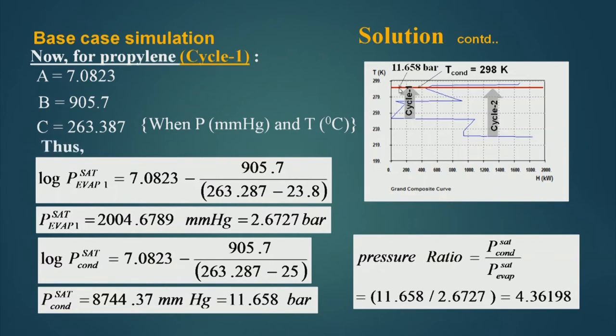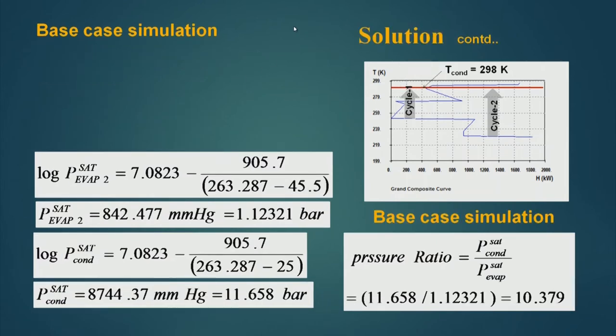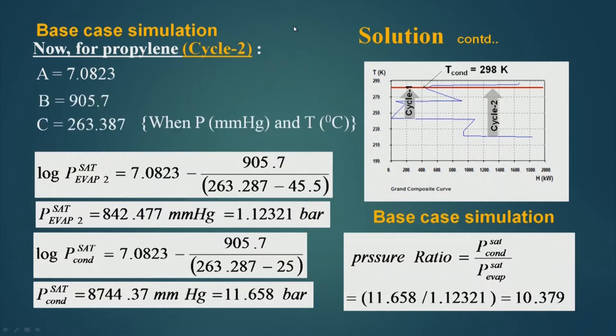The condenser is operating at 11.658 bar and the level 1 evaporator is operating at 2.6727 bar. From this pressure to that pressure, the vapor has to be compressed. Similarly, for cycle 2, the evaporator is operating at 1.12321 bar because cycle 2 is operating at a much lower temperature, so its pressure has to be lower.